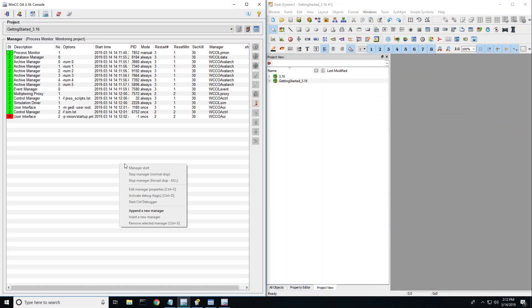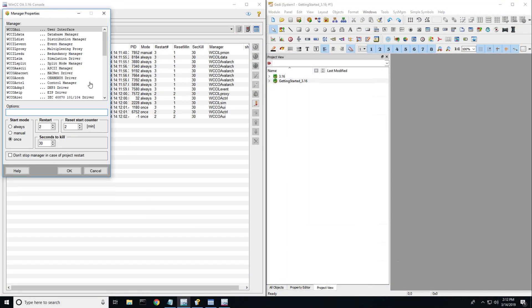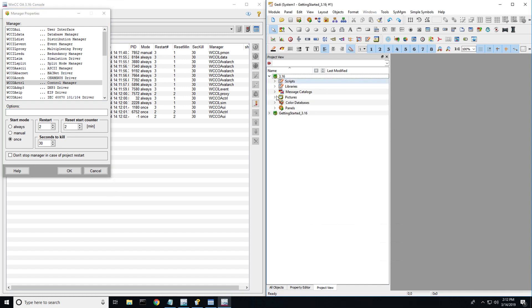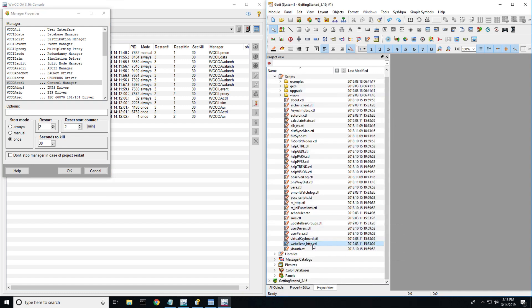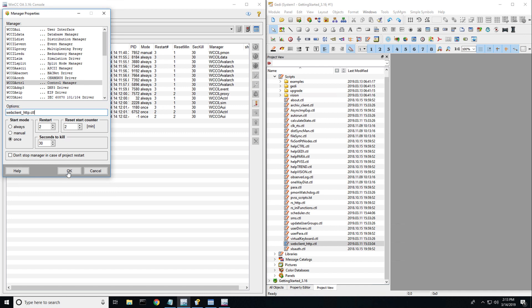The first thing we want to do is get our web server started. Append a new manager, add a control manager — we did a tutorial earlier on how to set up the web server. Drill down to webclient_http.ctl, write that syntax into the options line, set it to once, and click OK. Once it's up and running and the light's green, your web server is up and going.